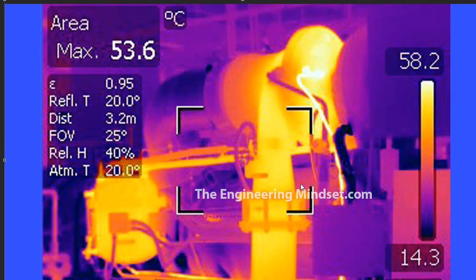Here is a thermal image of the discharge line coming out of the compressor, with the compressor at the top and the suction line there. The refrigerant enters the compressor, goes round, and is sent out through the discharge line into the condenser. You can see from here that it's going to be around 55 degrees Celsius — that's the temperature of the refrigerant coming out of the compressor and into the condenser.